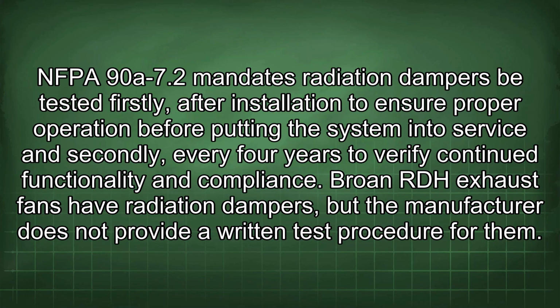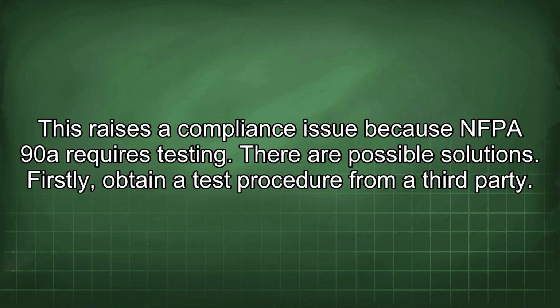NFPA 90A 7.2 mandates radiation dampers be tested, firstly after installation to ensure proper operation before putting the system into service, and secondly every 4 years to verify continued functionality and compliance. Broan RDH exhaust fans have radiation dampers, but the manufacturer does not provide a written test procedure for them. This raises a compliance issue because NFPA 90A requires testing.